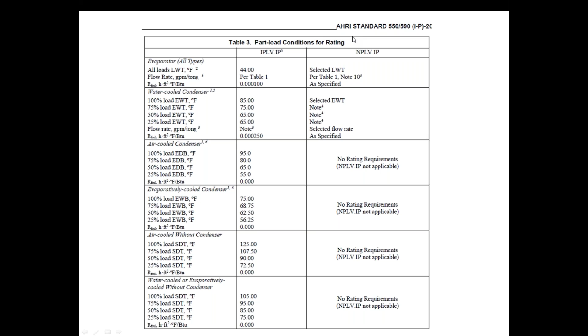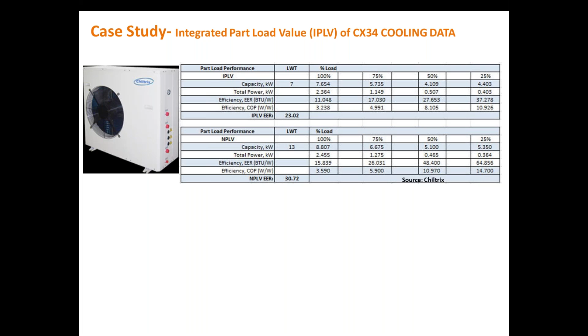One case study of IPLV and NPLV calculated on a Chiltrix chiller, CX34 model. As you can see, the part load performance at various loadings - 100, 75, 50, 25% - they have calculated the capacity, total power, energy efficiency ratio, COP, and finally EER, and IPLV based on EER. Second is the part load performance for NPLV, so NPLV for EER is given. So IPLV comes out to 23.02 as they have found, and NPLV comes to approximately 31. This is the type of data you will get when purchasing, or the manufacturer will provide in the product catalog where the IPLV and NPLV values are mentioned.